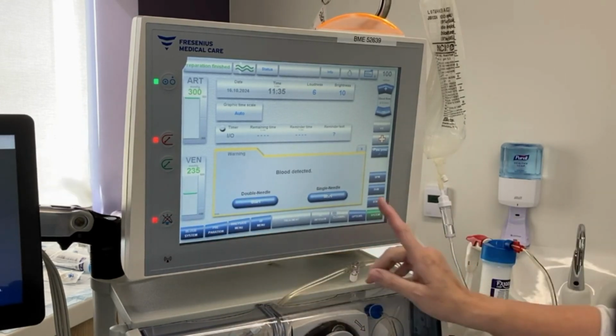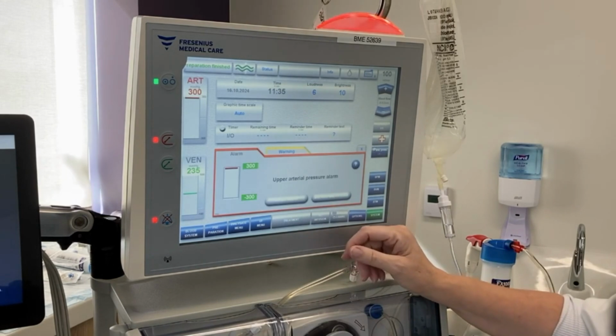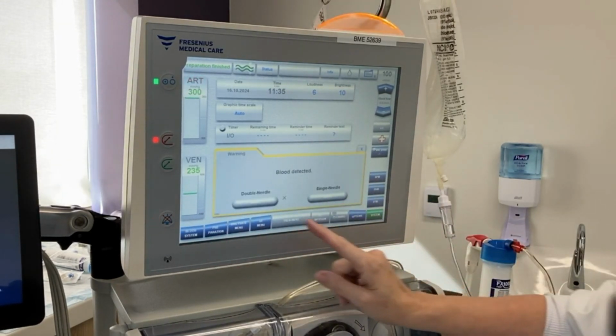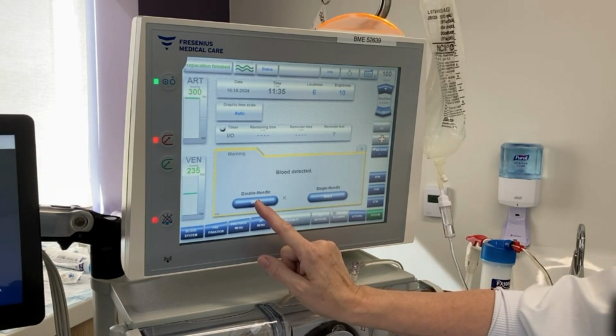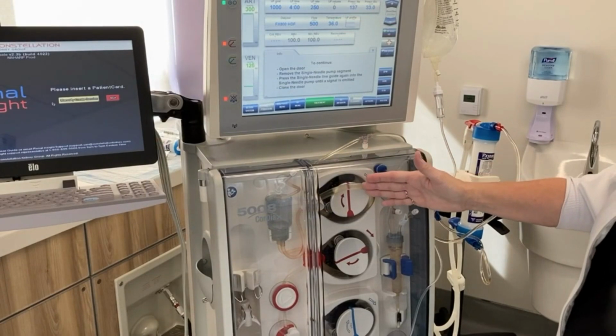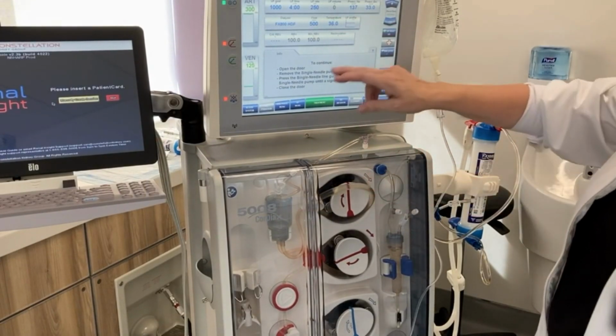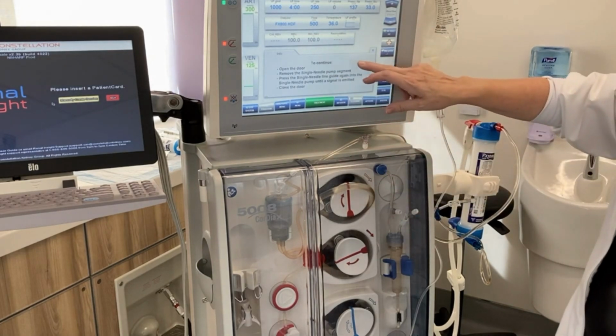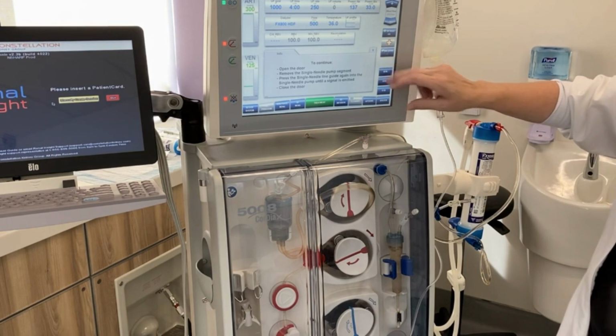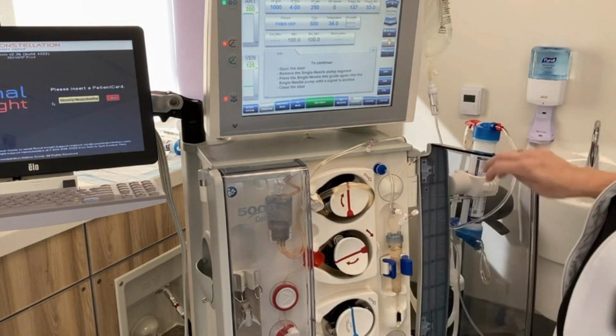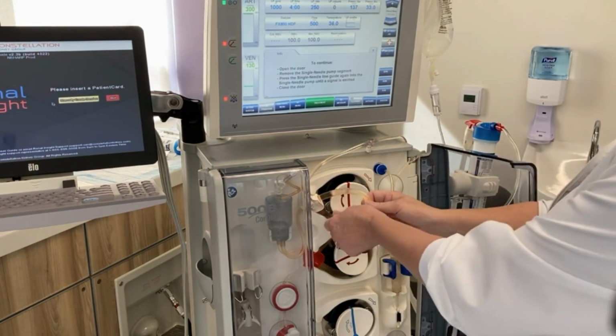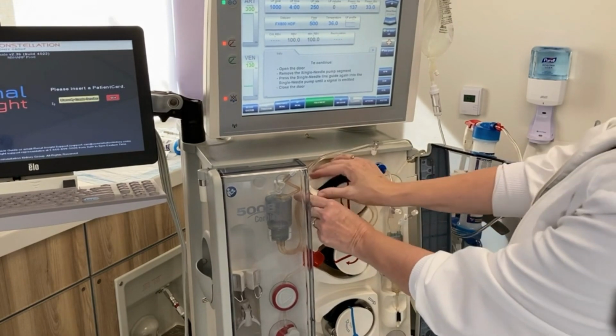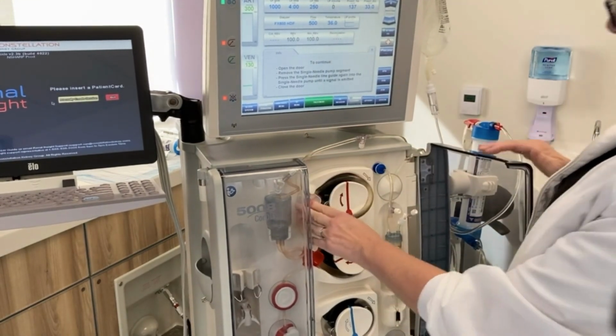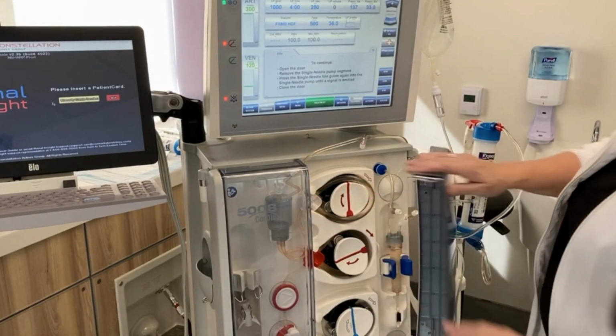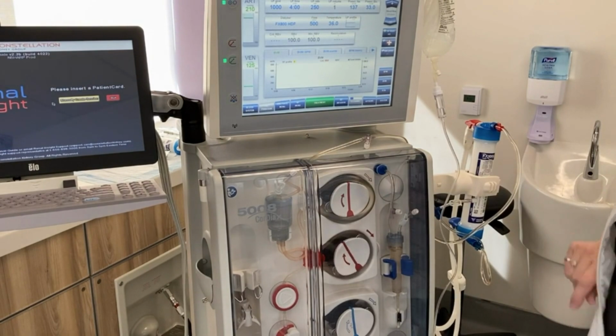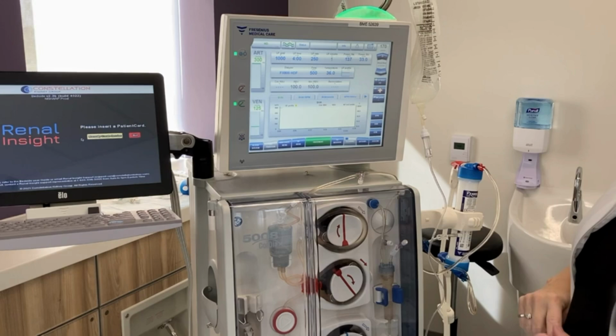So once it's detected the blood, it gives us the option. We can either do the double needle or single needle. And we've got double needle now, so we can go ahead and choose double needle. At that time, it's going to pop out this first arterial pump line. So it's giving you instructions here of what to do. So it says to continue, open the door, remove the single needle pump segment, and then press it in again until it emits the beep. Okay, it's left loose here. We close the door. We're able to continue on with 2 needle dialysis.